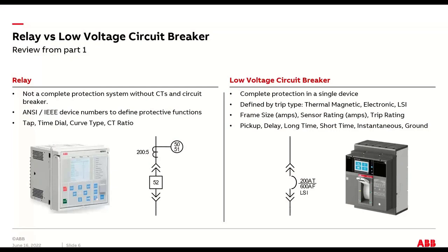Between the protective relay, medium voltage, high voltage protection versus low voltage, the relay itself is only a piece of a larger system. Whereas the low voltage breaker is a single package with everything built into it. So it's the brains plus the switch. It's all been pre-engineered. You really only have to call out that one device, the low voltage breaker, and it's a complete system. Relay is not like that.